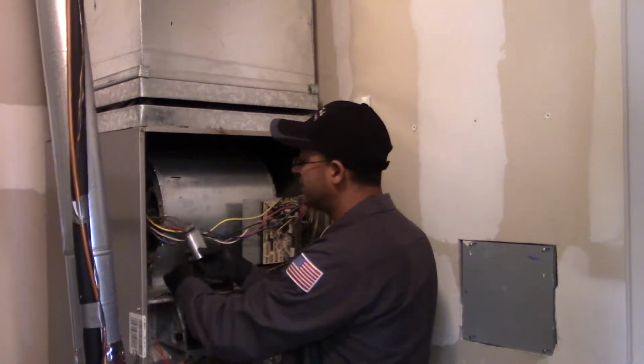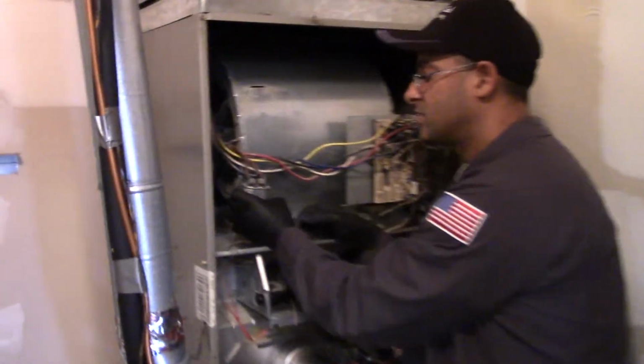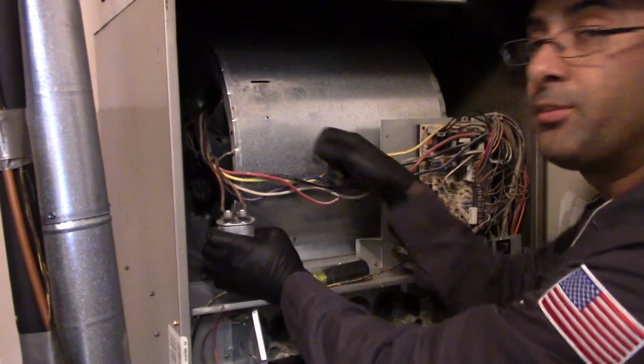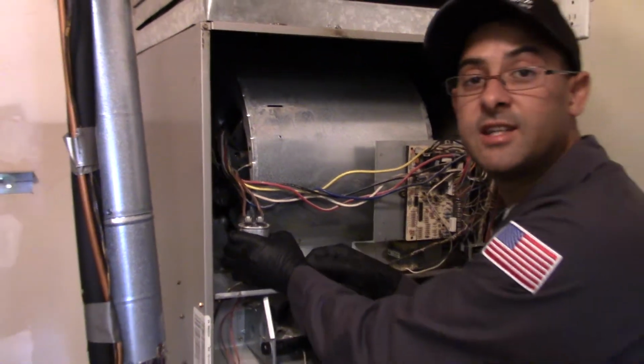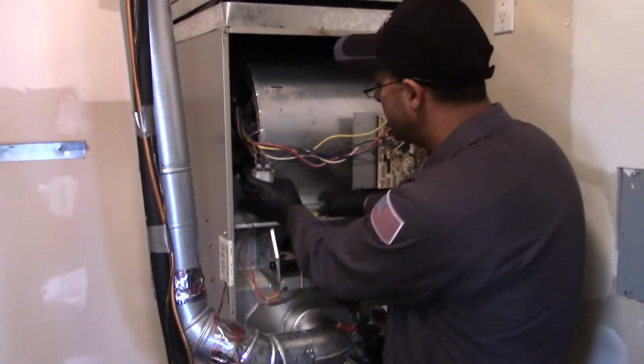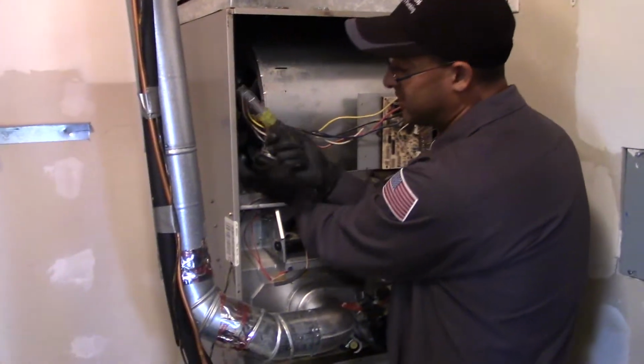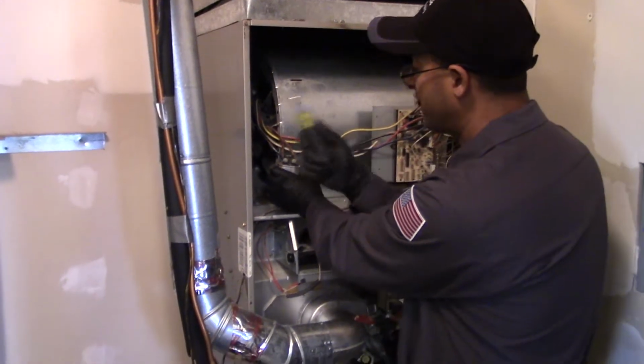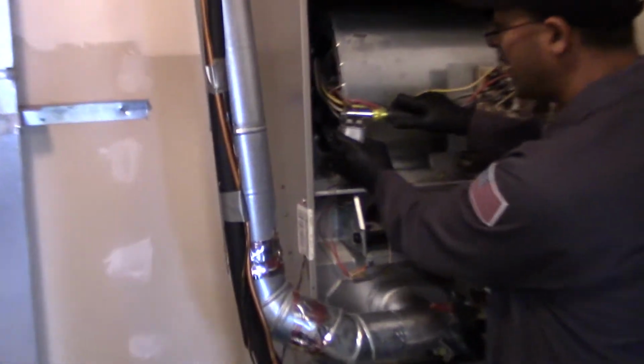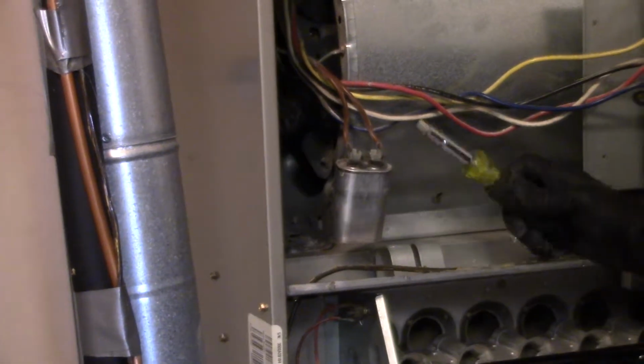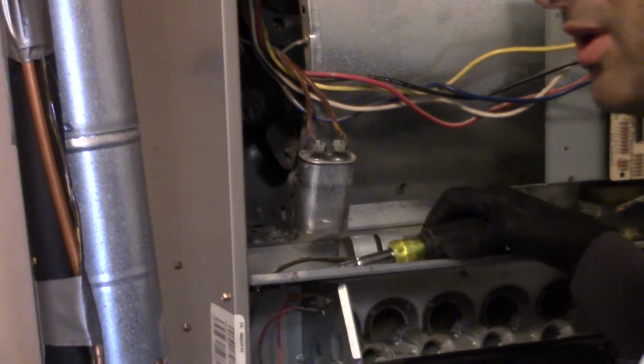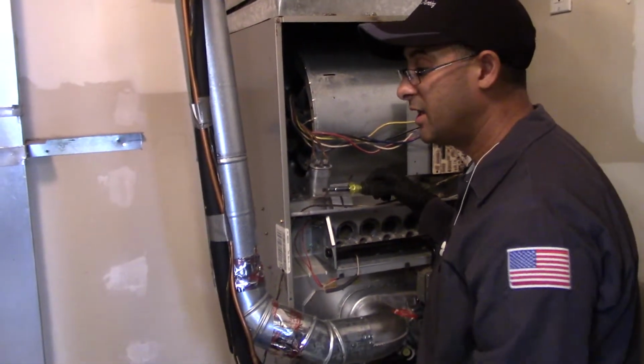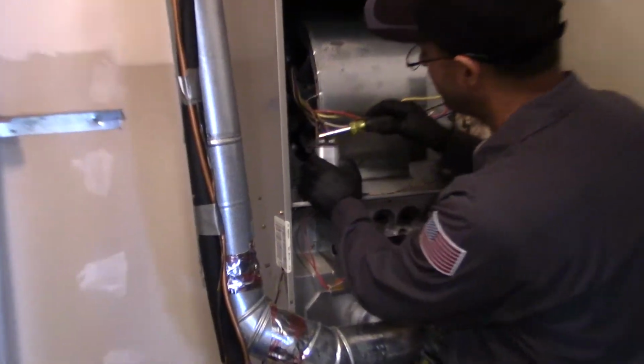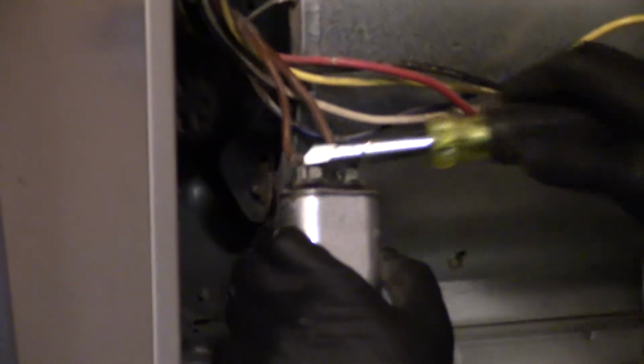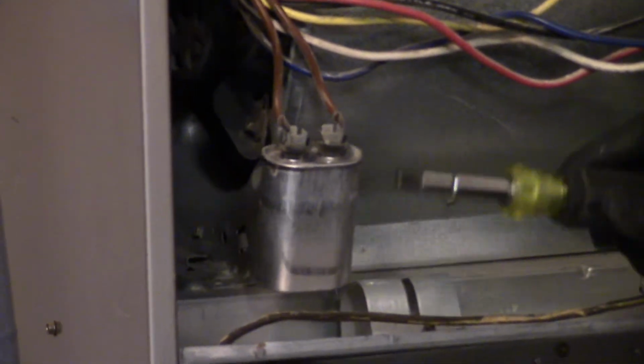I never want to touch these wires because this capacitor stores electricity to help the motor run. If I touch these, there's a good chance I can get shocked. So what I want to do is run an insulated screwdriver across here—make sure you have a rubber insulated screwdriver, not metal. Sometimes you might see a little pop, especially if the power is still plugged in. But if it's storing charge, it can do that. By doing this, we're shorting the capacitor, bleeding the voltage out of it, making sure we're not going to get shocked.